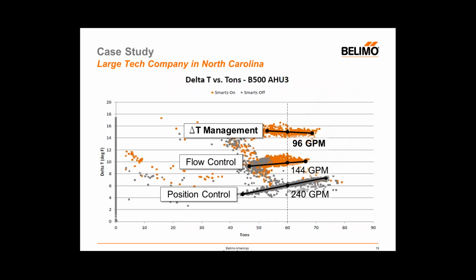Now, granted, in this case, we started with an air handler that was running at a 6 degrees delta T, and it probably had a 16-degree coil in it. So we had a substantial problem which we could correct. But the impact shows that the physics behind this is valid. We can use less water in a lot of cases to meet the same demand.